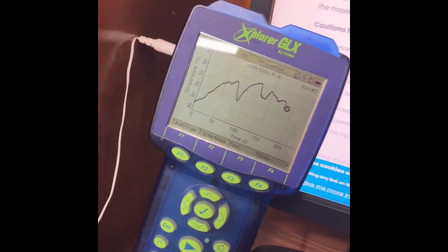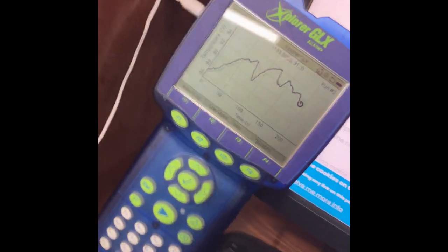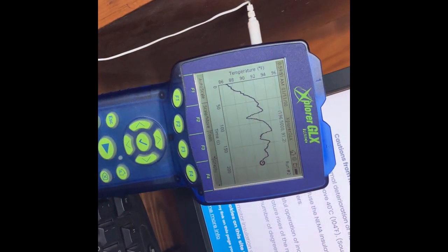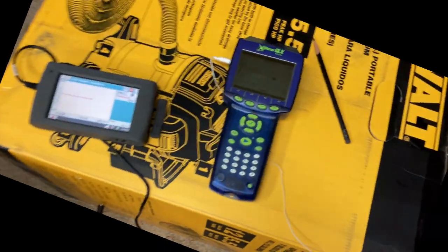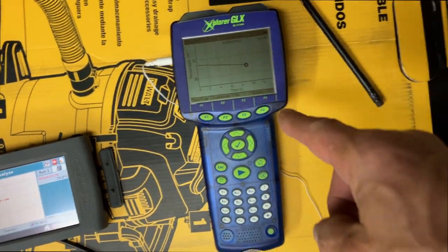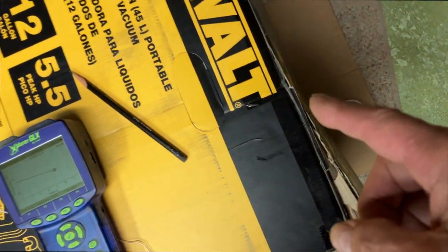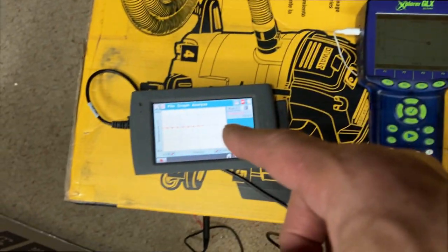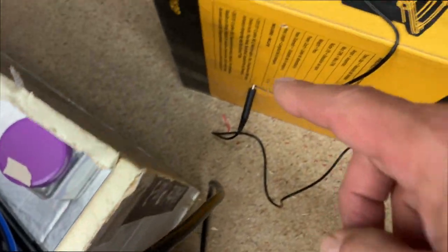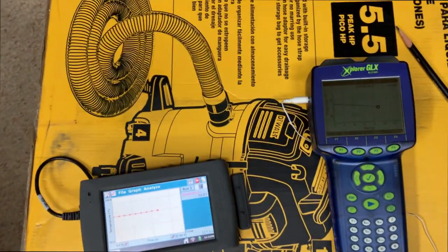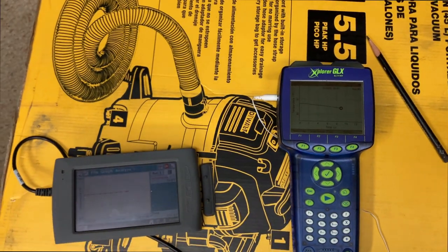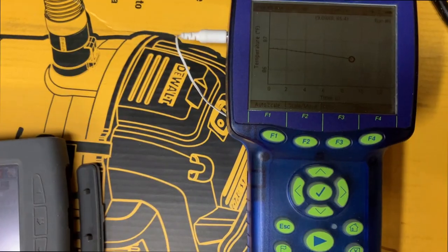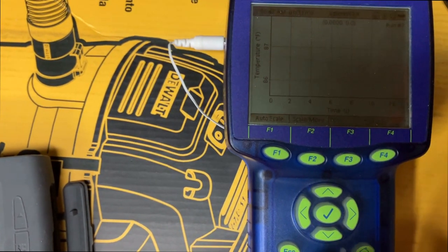We're going to see what the temperature is right at the thermal overload and see what temperature it actually craps out at. Okay, this is what we tied to the heater right by the over temperature limit switch, and this we're going to monitor box temperature, and we set it on low heat, and my interest is to see at what point it over temperatures.